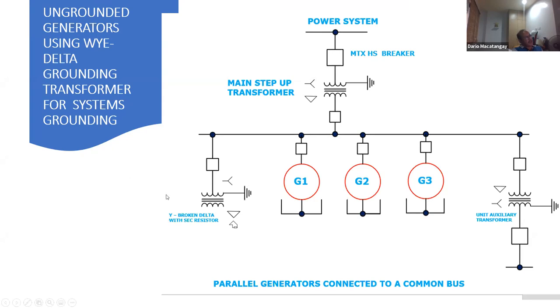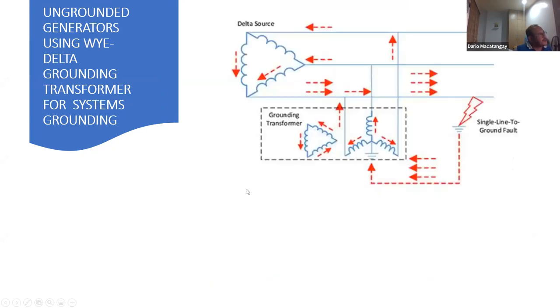Now to see an example of how the current flows, let's go to the next page. This is using a Y delta grounding transformer, right? You can see here, this is your delta ungrounded generator. When you have a ground fault here, the path of the current will be here. You see that coming through the neutral of the Y side of the grounding transformer. Here it goes back, it divides here and combines here and there. So you have a complete path, okay?